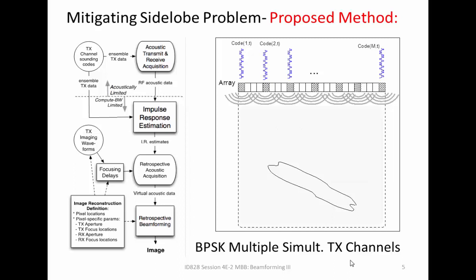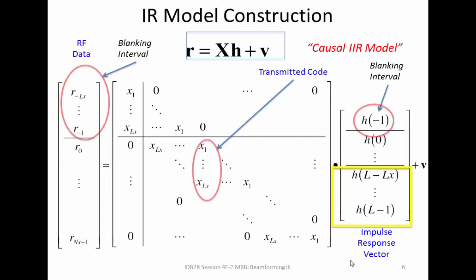We use this as a channel probing sequence and then estimate, using a model-based estimation procedure, all the impulse responses from the transmit to each of the received channels. This could be a sparse transmit or expanded apertures — partially focused or however you would choose. Once we get the impulse responses, we retrospectively use those by transmitting waveforms after the fact, applying transmit beamforming and receive beamforming all within this model.